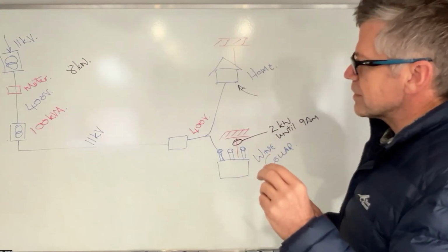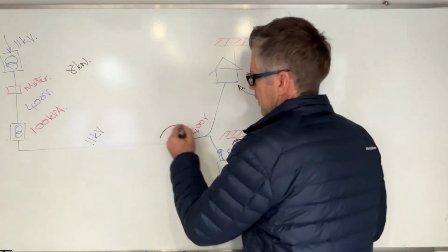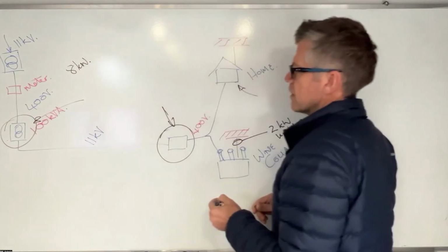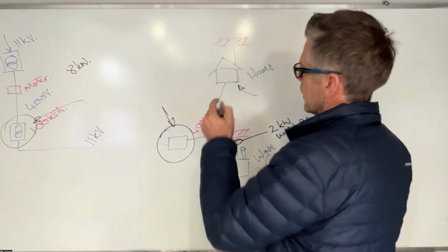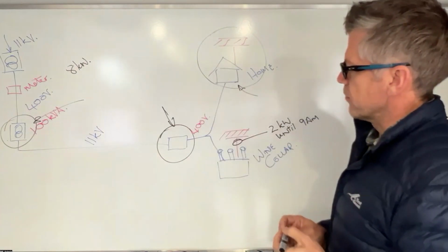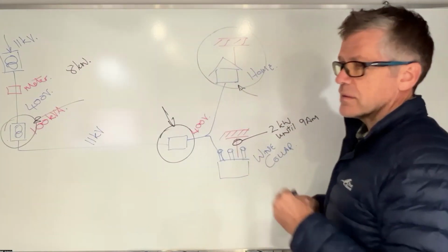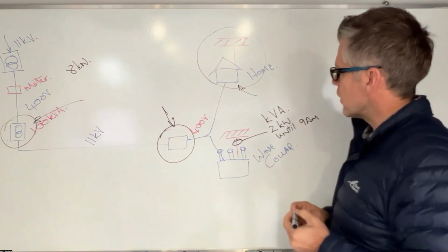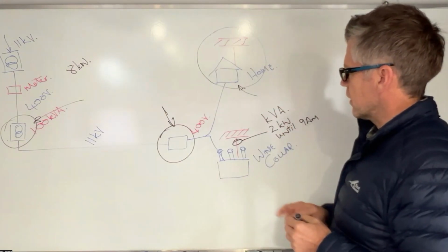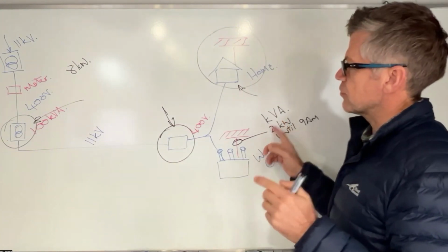So what I'm thinking, where some of those losses are going, is into that transformer, and what we don't have is the data for the home. I think undoubtedly the KVA issue is generated by a load at the wine cellar. We'll have to find the KVA issue.